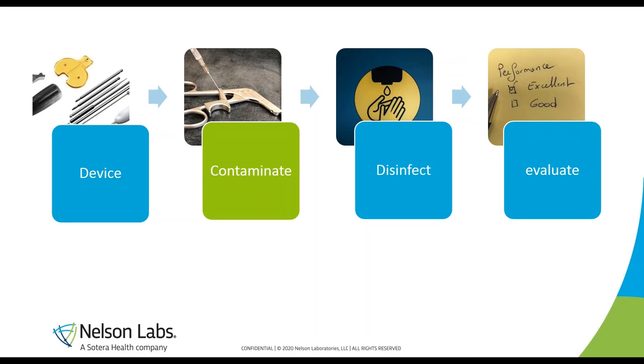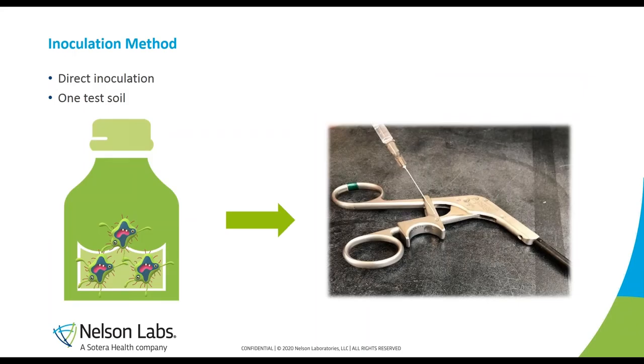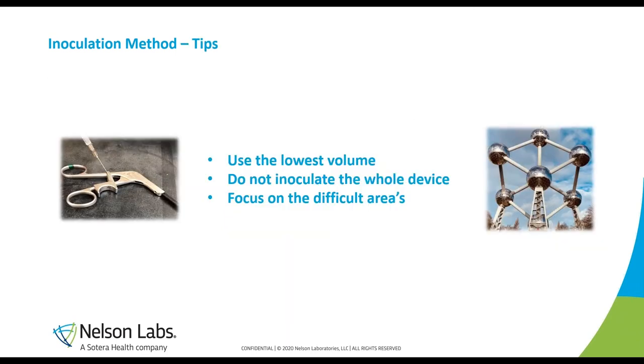Step two: contaminate the device. We take microorganisms and bring them onto the device — for example, applying droplets of microorganisms onto the surface. Use a low volume of droplets with a high concentration of microorganisms instead of a large volume. Do not inoculate the whole device — focus only on the difficult areas. Define those areas in your validation protocol so that lab personnel know exactly where to apply the microorganisms.